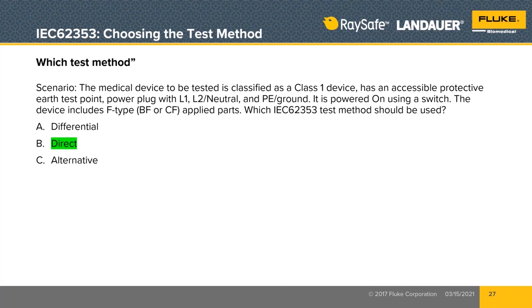Even 60601-1 would still be okay. Remember, the only reason that we do not choose 60601-1 is because there are tests within it that will shorten the useful life of the medical device. Therefore, we don't want to use it for routine electrical safety testing, which is why the 62353 exists anyway. For those of you that picked differential, I'm not going to say you're wrong. I'm just going to say there are good reasons why we would have picked direct, given this scenario.